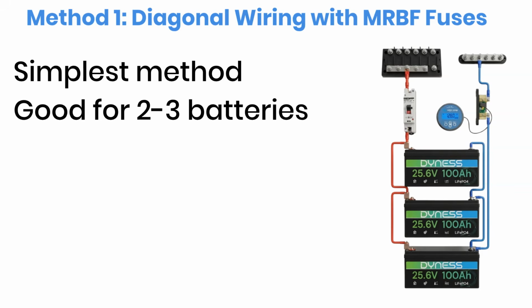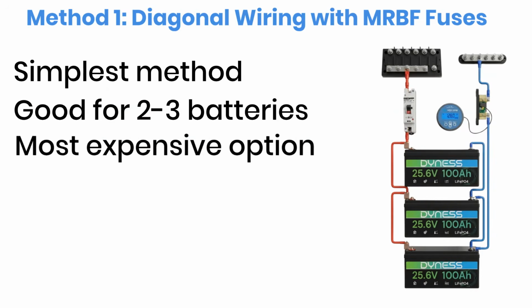The biggest drawback of this method is the cost. Since every battery connects directly to the main bus bars, each cable normally needs to be sized for the maximum current that battery could deliver. On top of that, MRBF fuses and their terminal blocks are generally more expensive than many other fuse options.